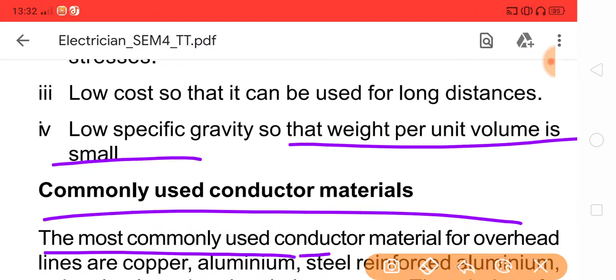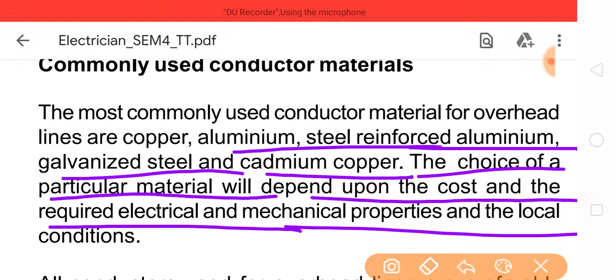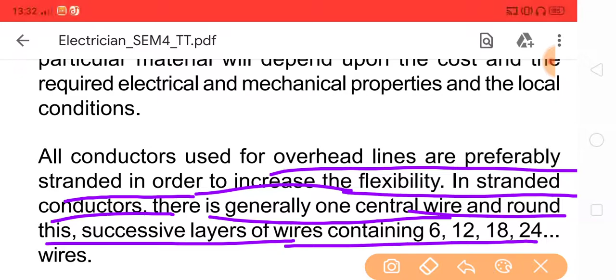Commonly used conductor materials. The most commonly used conductor materials for overhead lines are copper, aluminum, steel-reinforced aluminum, galvanized steel, and cadmium copper. The choice of a particular material will depend upon the cost, the required electrical and mechanical properties, and the local conditions. All conductors used for overhead lines are preferably stranded in order to increase flexibility. In stranded conductors, there is generally one central wire with successive layers of 6, 12, 18, 24 wires around it.